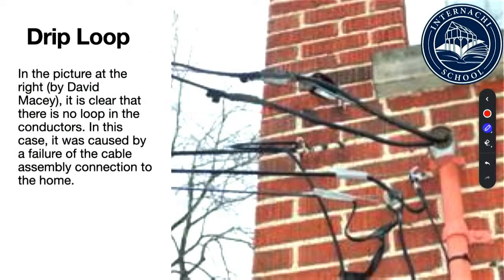The drip loops: sometimes the service points of attachment come loose or break loose, and then the wires go straight. The problem with this is if water from rain comes in here, they're afraid it's going to come down the service mast and create a problem. And that's the whole purpose of these drip loops. As water comes down here, it's going to drop off and not come into the electrical system.